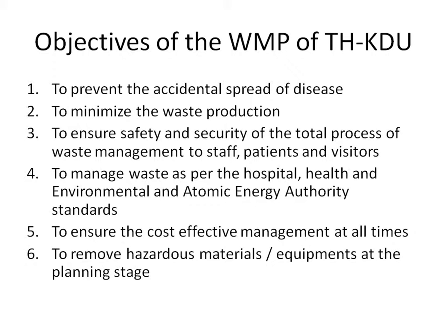One of the problems is that what we have calculated is generally what we produce. What will happen after a while if you want to discard your CT scanner? Whatever the materials, hazardous, maybe radioactive, you should sign up with the supplier when you buy them, so that once we complete, they take it back after 5 years.